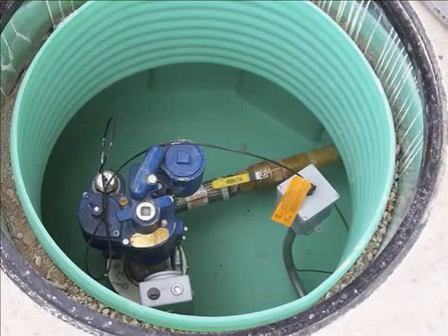The pumps commonly used for fuel transfer are submersible turbine, centrifugal, or positive displacement gear pumps. Submersible pumps are widely used for gasoline service stations and also for diesel power systems. They have a low cost relative to their high flow rate and avoid the suction piping and priming problems associated with other pumps.